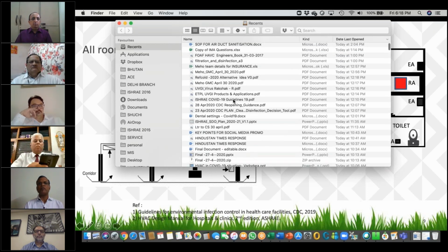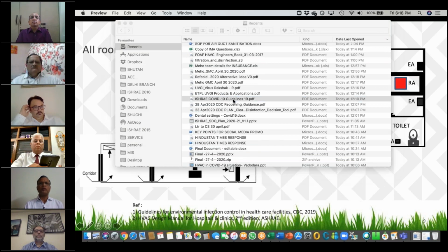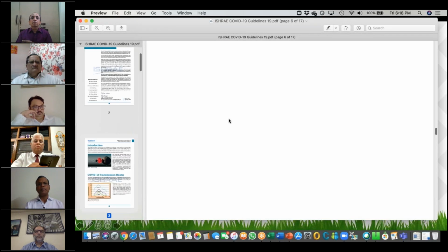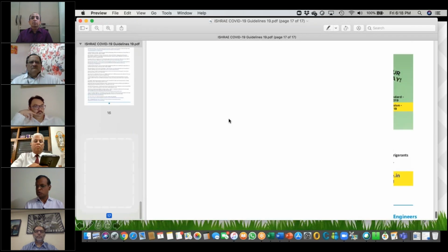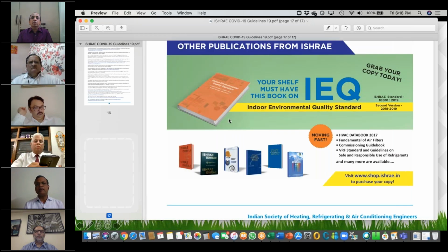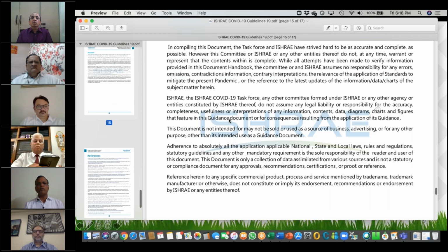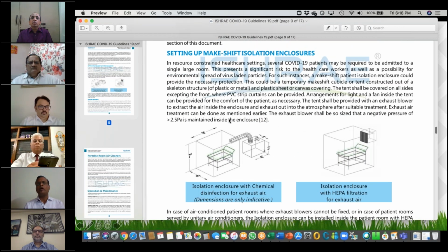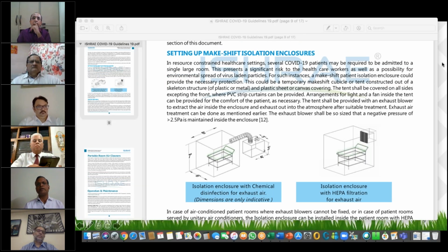We need to contain from the source. If there's a source of droplets or contaminants, they need to be contained and trapped as close as possible to the source. But that's easier said than done - we may not be able to do it 100%, so there is some likelihood of infiltration and exfiltration of contaminants from the source point.